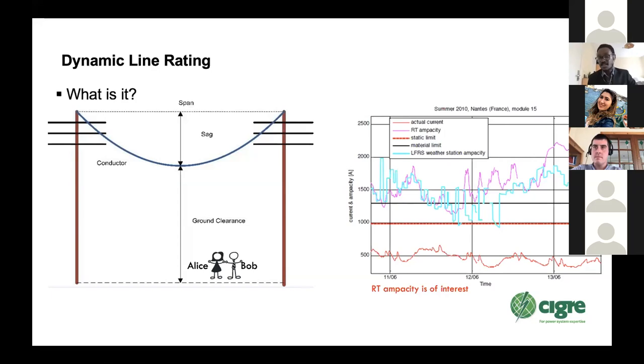And as you can see in the graph to the left, a typical line will have a static limit, which would be the maximum amount of current that could pass through the line based on the ground clearance limitations. So you could have a limit of 1,000 amps, which is the case in the image in front of you. However, using dynamic line rating, if we could monitor the actual conditions in the line, we don't have to follow the conservative estimates usually employed in the design stage, then the capacity of the line could be increased. As you can see in the graph, there's a 50% increase during certain periods and up to 100% increase if you look at the purple line, which is the real-time capacity.